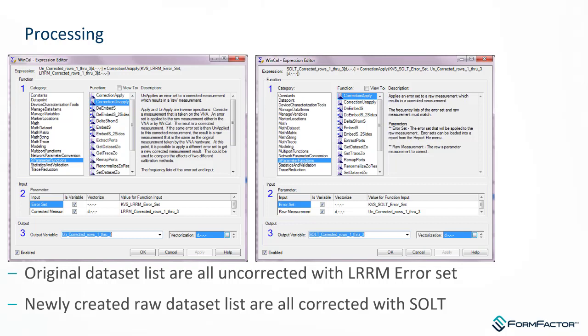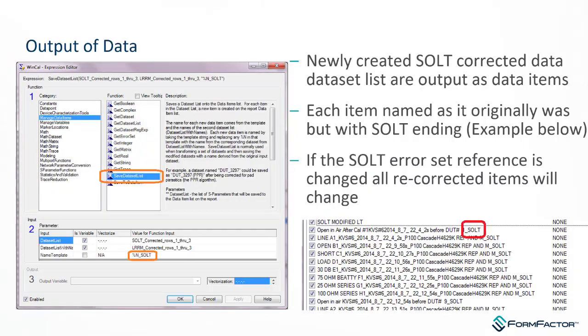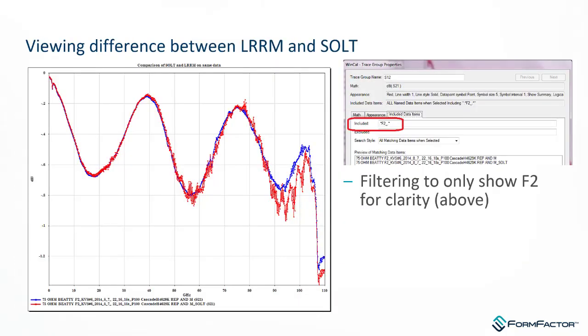Instead of remeasuring everything, we can simply take the existing results — we still have the error set — unapply the correction to get back to raw data, and then reapply a newly computed SOLT error set. With one measurement, you can conveniently look at a calibration comparison. In this example, we create a new data set and append the name 'SOLT.' The result shows before and after: blue is the LRRM measurement and red is the SOLT, so you can clearly see the calibration comparison.